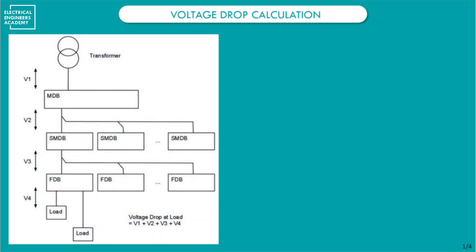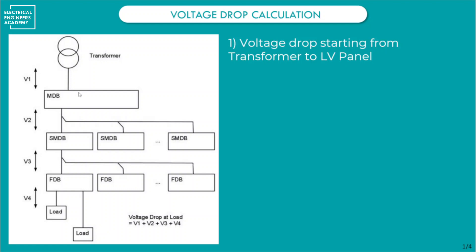To understand this four percent limitation properly, let's look at a typical power distribution scheme. We have the transformer supplying the MDB, then several SMDBs feeding final DBs, and finally the loads such as sockets, equipment, and light fittings. That four percent is measured from the transformer's low-voltage side all the way to the final load. V1 represents the voltage drop from the transformer to the LV panel — usually a short distance of 15 to 20 meters.